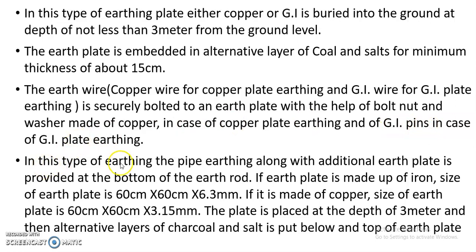Next point is, in this type of earthing, the pipe earthing along with additional earth plate is provided at the bottom of the earth rod. That means it is the extension of our pipe earthing. If earth plate is made up of iron, then size of earth plate is about 60 into 60 into 6.3 mm. If it is made up of copper, size of earth plate should be 60 cm into 60 cm into 3.15 mm. The plate is placed at the depth of 3 meter and then alternative layer of the charcoal and salt is put below and the top of the earth plate. So we have to design this plate earthing. So we have to consider these parameters.